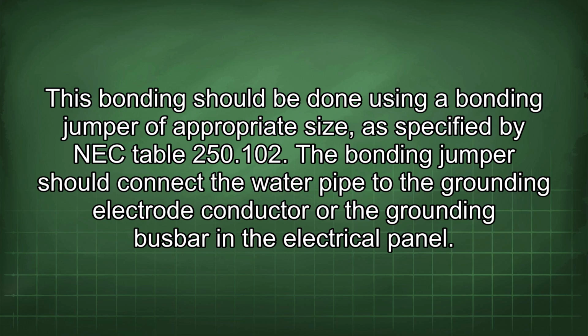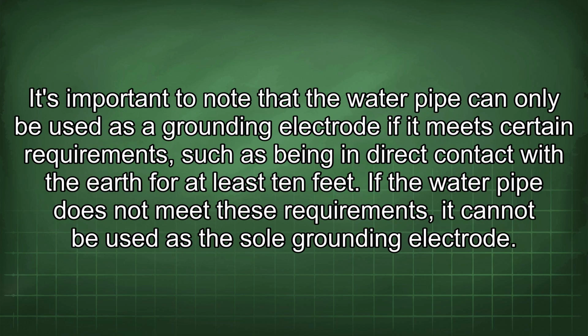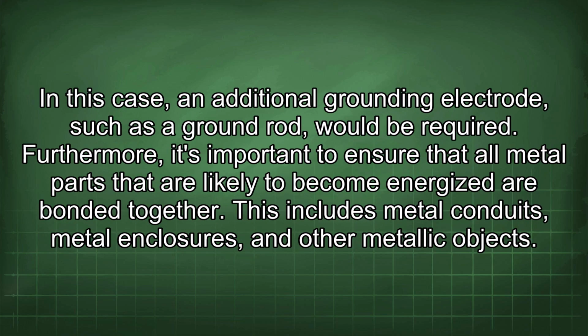electrical panel. It's important to note that the water pipe can only be used as a grounding electrode if it meets certain requirements, such as being in direct contact with the earth for at least 10 feet. If the water pipe does not meet these requirements, it cannot be used as the sole grounding electrode. In this case, an additional grounding electrode, such as a ground rod, would be required.